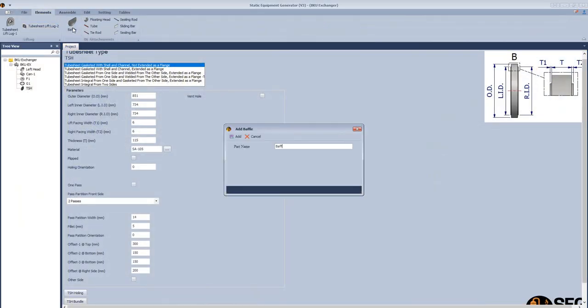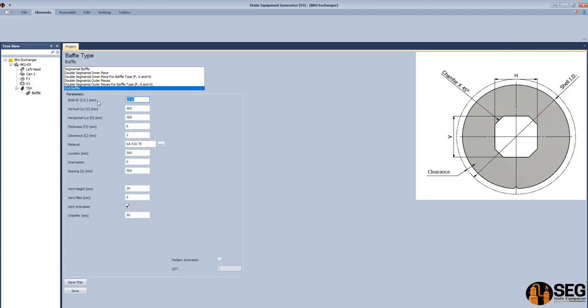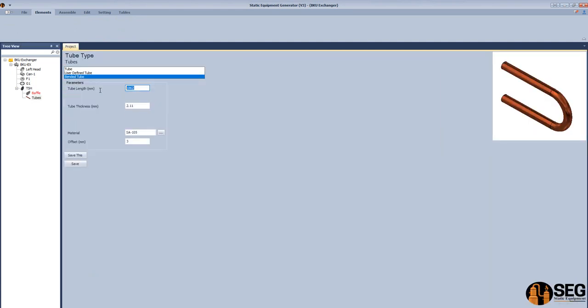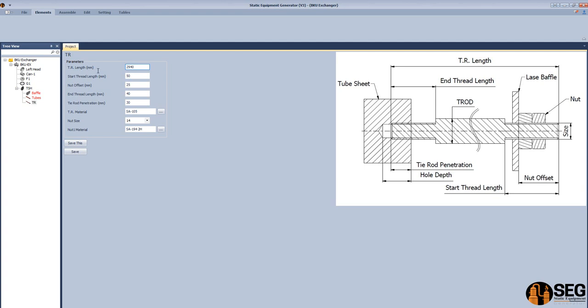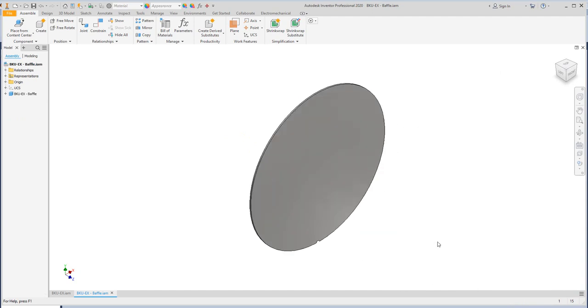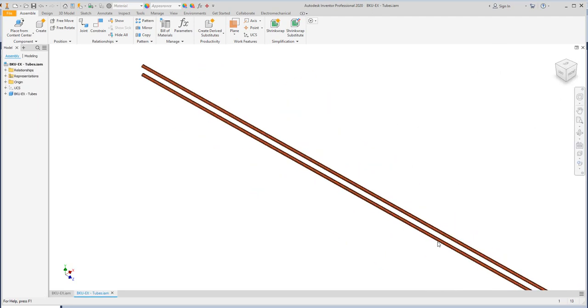Now let's add a baffle — a support baffle. Let's select end baffle. Define the inside diameter of the shell, define the clearance, no cut in the middle. Define the spacing and the location. Define the vent hole and number of baffles. Now let's add a tube. After creating it, let's select a bent tube, not a straight tube. Now let's add a tie rod. Define the length, thread length at the start, no offset, thread at the end, tie rod penetration, and diameter of the tie rod. Now let's create the new 3D model for those parts — baffles, tube, and tie rod.